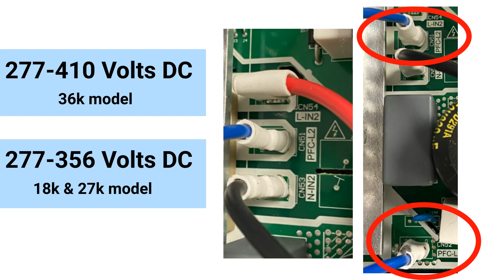If the voltage isn't in range, then check whether the inductance of the PFC module is good by testing NIN2 and LIN2, marked by black and red wires and white plugs. If the inductance is good, the resistance of the two ports should be 0. If it isn't 0, then replace the inductance. If it is 0, replace the PFC module.